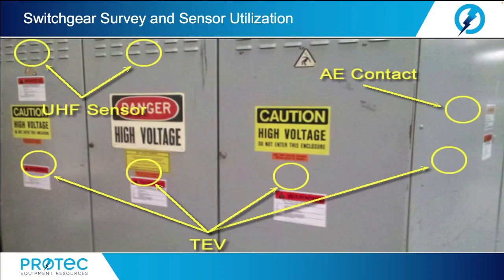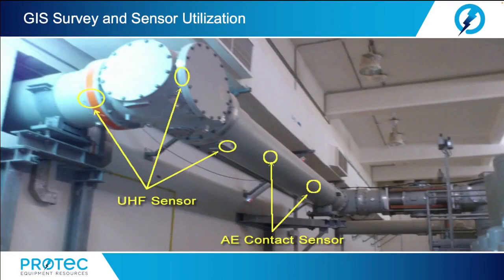Now, here we show some sensor utilization during a switchgear survey, where UHF sensors can be used anywhere where we have openings in the metal enclosures. Also, acoustic emission and ultrasonic contact probes can be used along the cabinet doors and panels. Also, we can take transient earth voltage measurements along the panels.